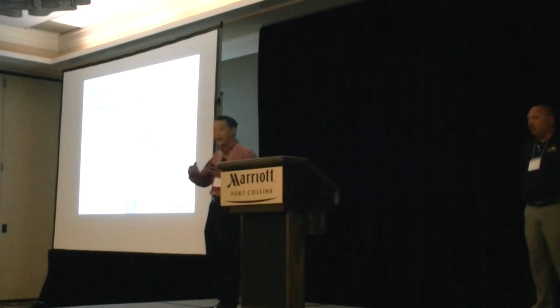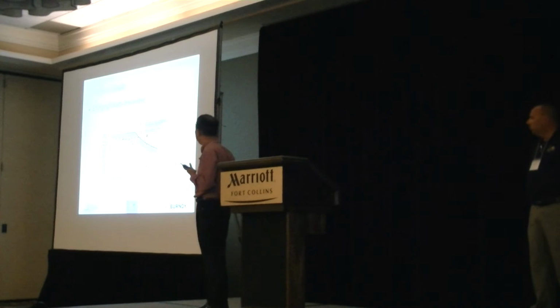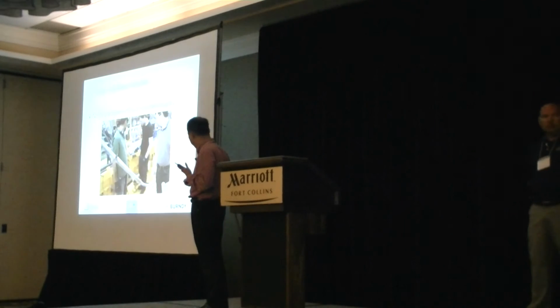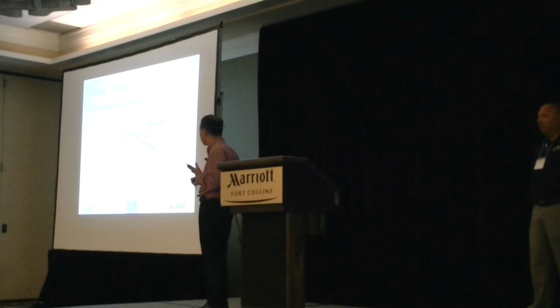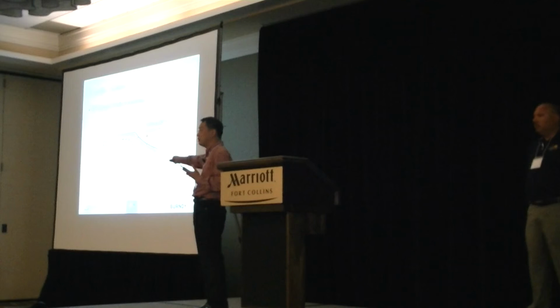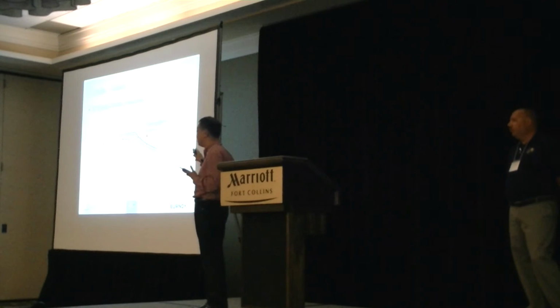So what we did next is we took the Burndy strain charts and plotted where our test results would land on the strain charts. And you notice that a lot of times our test results exceeded the Burndy strain charts, which was good. That's what we wanted. Because if it fell below, then we would be a little bit worried, in that we wouldn't know what we would get if we installed the conductor based on the Burndy chart. But because they were exceeded, we had a good confidence that we could use the charts.